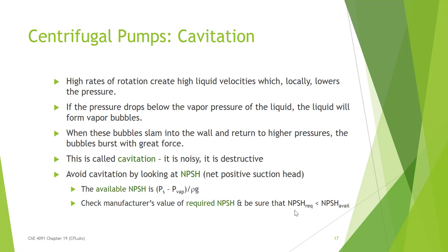You'll know you have cavitation in your system by the noise, but you can avoid it by planning ahead. To do that, we look at the net positive suction head (NPSH) — this is the pressure on the intake side of the pump. We simply want to make sure we have enough pressure on that side so that we will always be above the vapor pressure. That's something you want to always verify in your system.